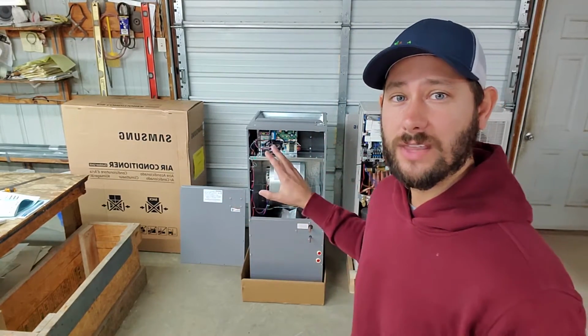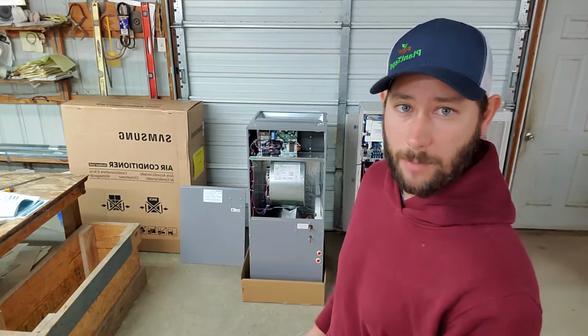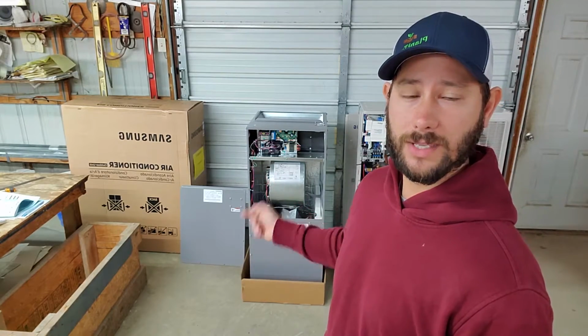I change a little option setting on the wired controller, which I've got a video about. If you guys want to check that out, check out Tips for Technicians. I change a little option setting. I'm able to choose the indoor sensor. So the air pulling across that coil, it's going to choose that sensor. So you're keeping that unit warmer. You're keeping that duct warmer.